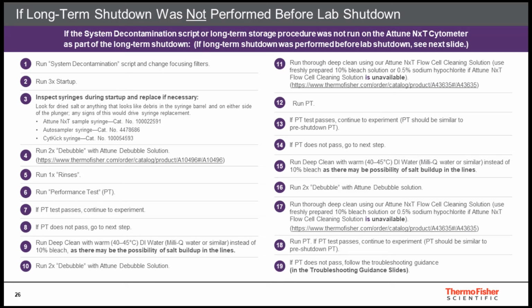Following the deep clean, run the debubble script twice. Following that, run deep clean again. However, instead of using 10% bleach, use the Attune NxT Flow Cell Cleaning solution. Just remember, you need to dilute your flow cell cleaning solution 1 to 3 in DI water. After these steps, run the performance tracking beads to see if the instrument passes.